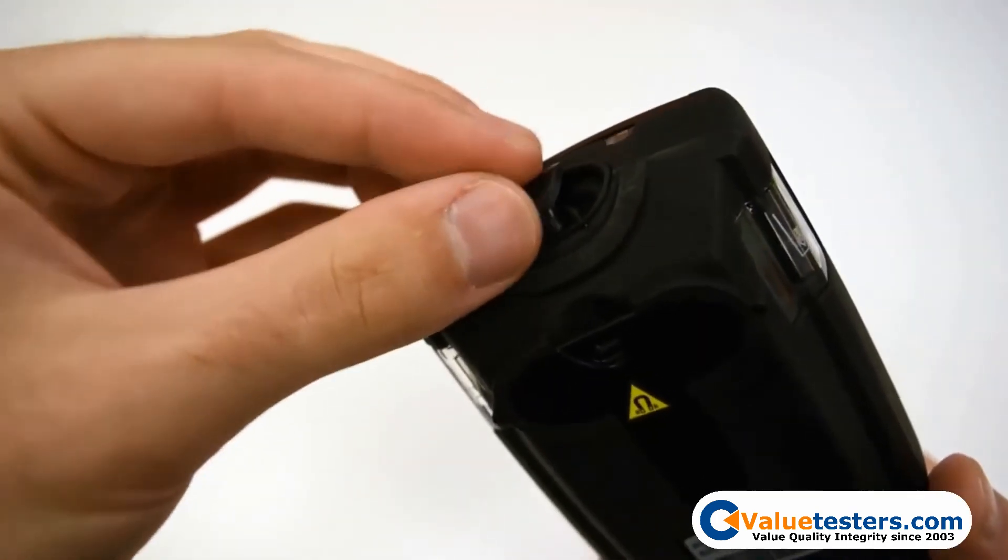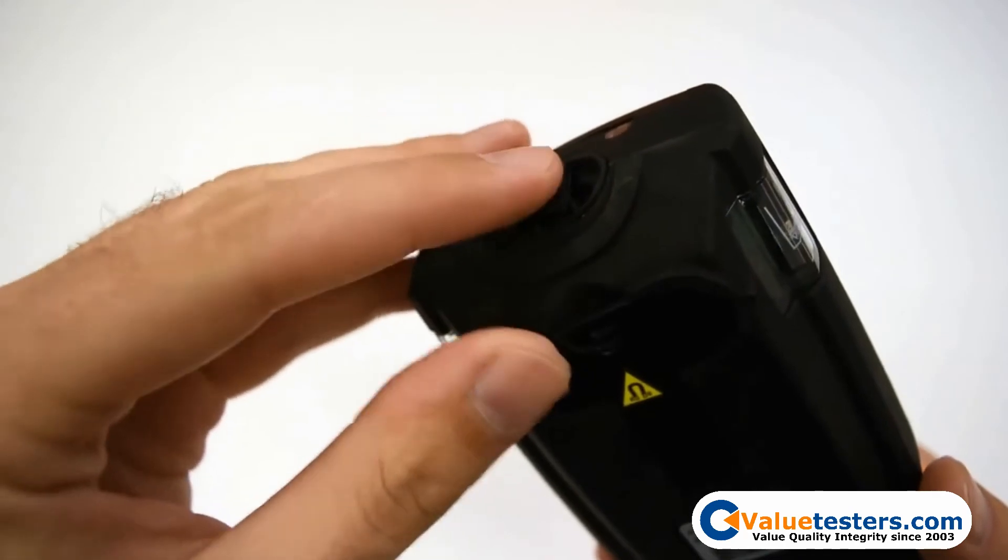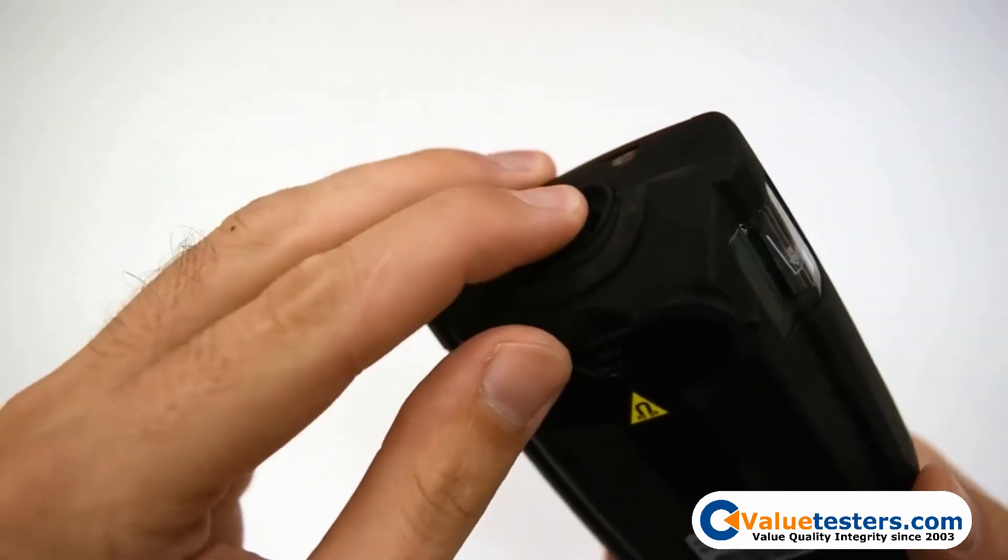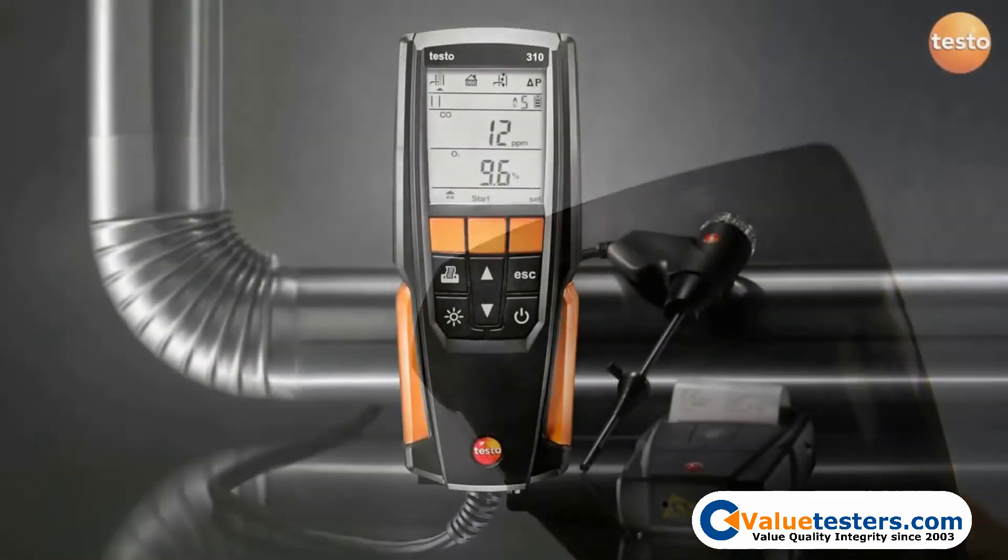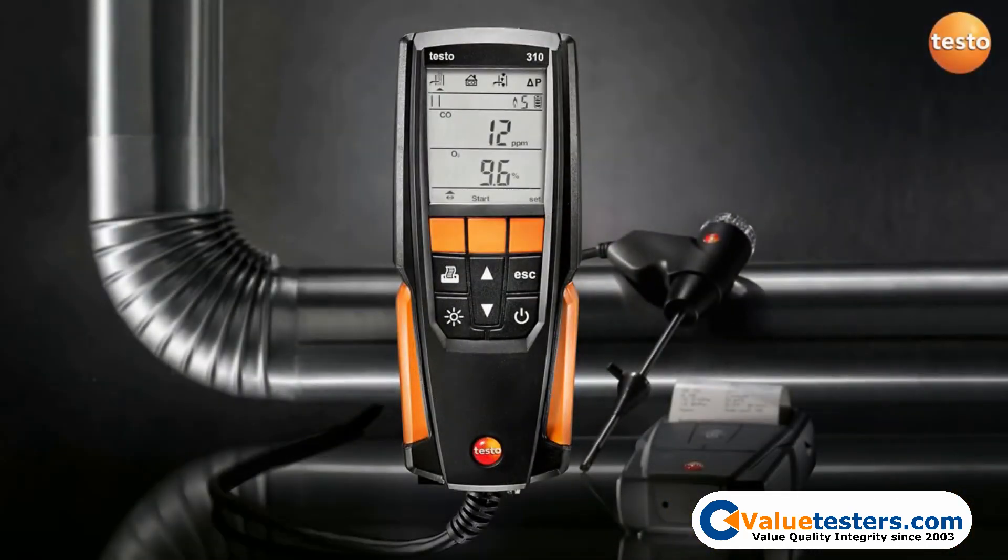Once the condensate trap is empty, be sure to fully seal the condensate plug. Leaving the plug out or not fully seating the plug will cause air to be pulled into the system and lead to measurement errors.